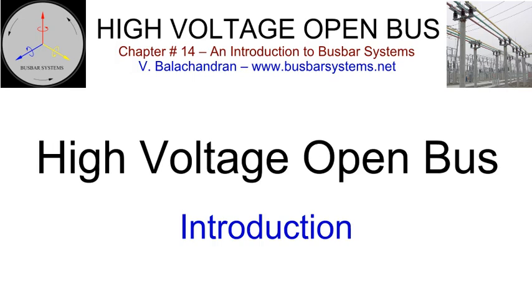High voltage open bus. Introduction. High voltage open bus are air-insulated, current-carrying conductors, clamped to insulated supports as in the case of switchyards. Open bus bars find applications both outdoors and indoors and in AC and DC systems. The present discussion will primarily focus on rigid aluminium conductors installed in outdoor switchyards.